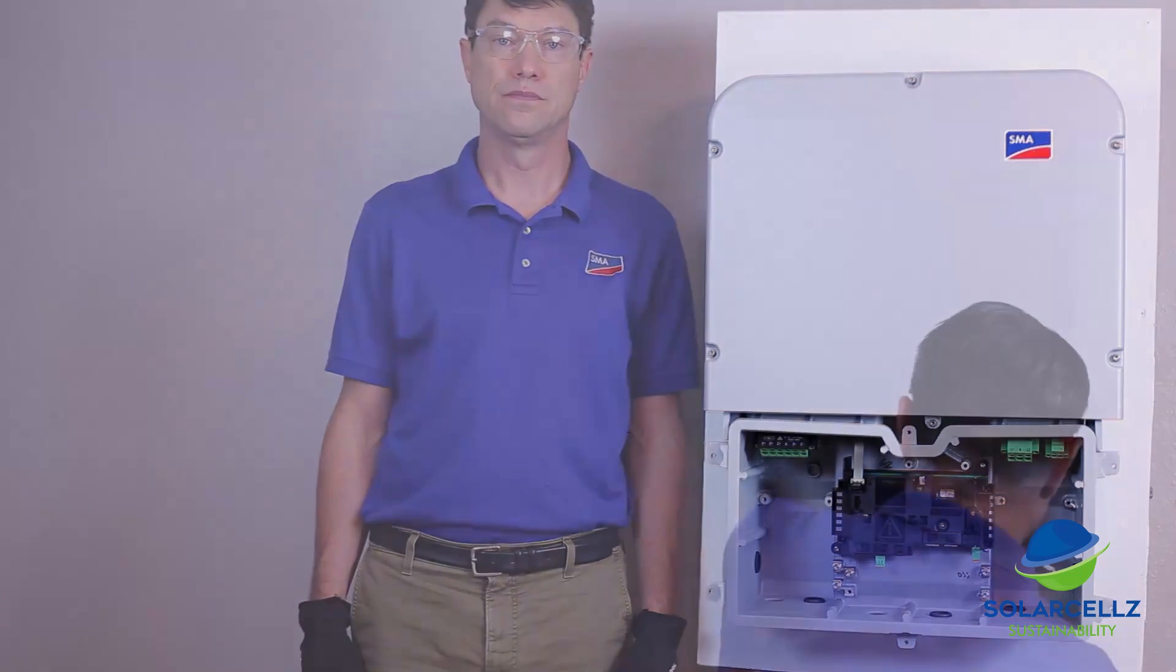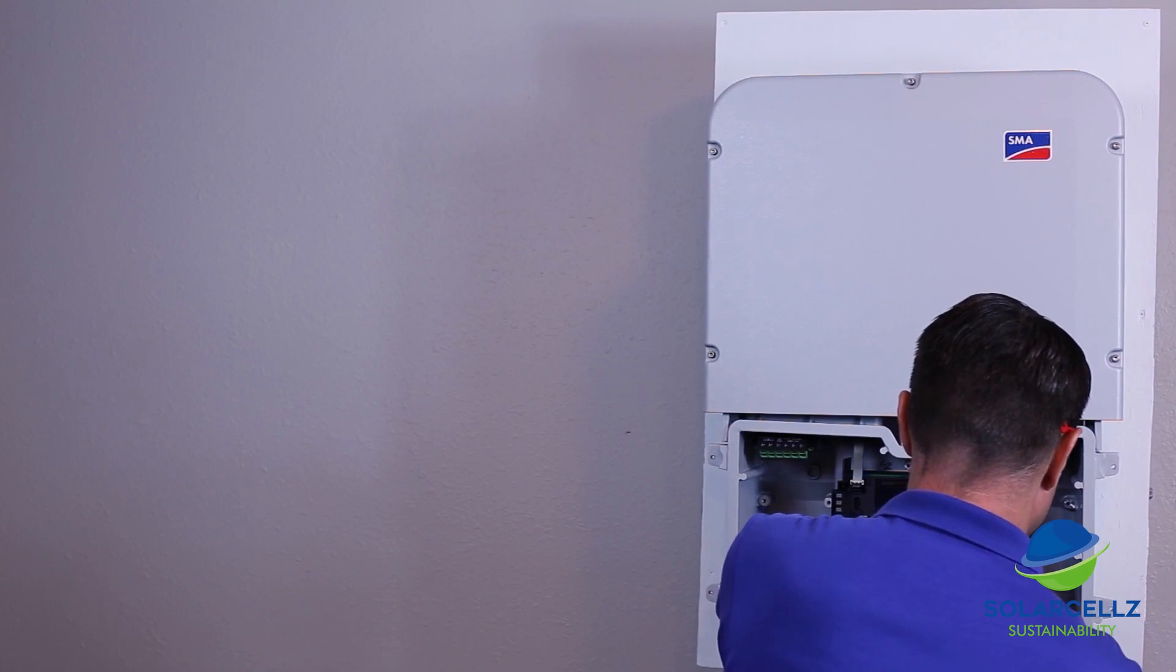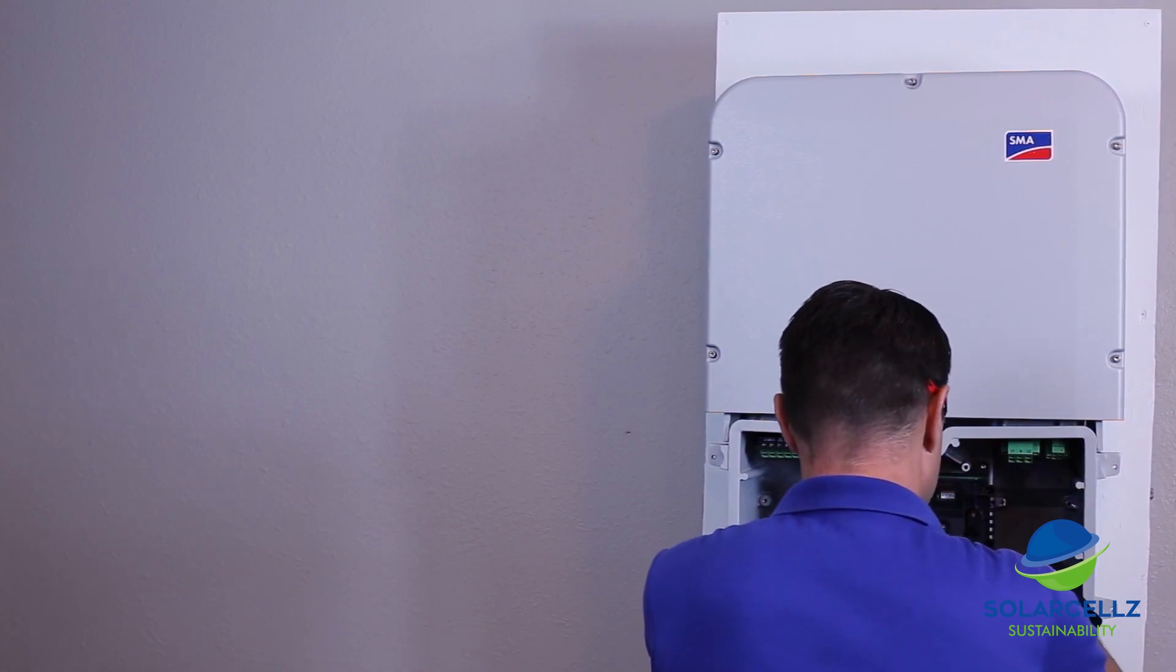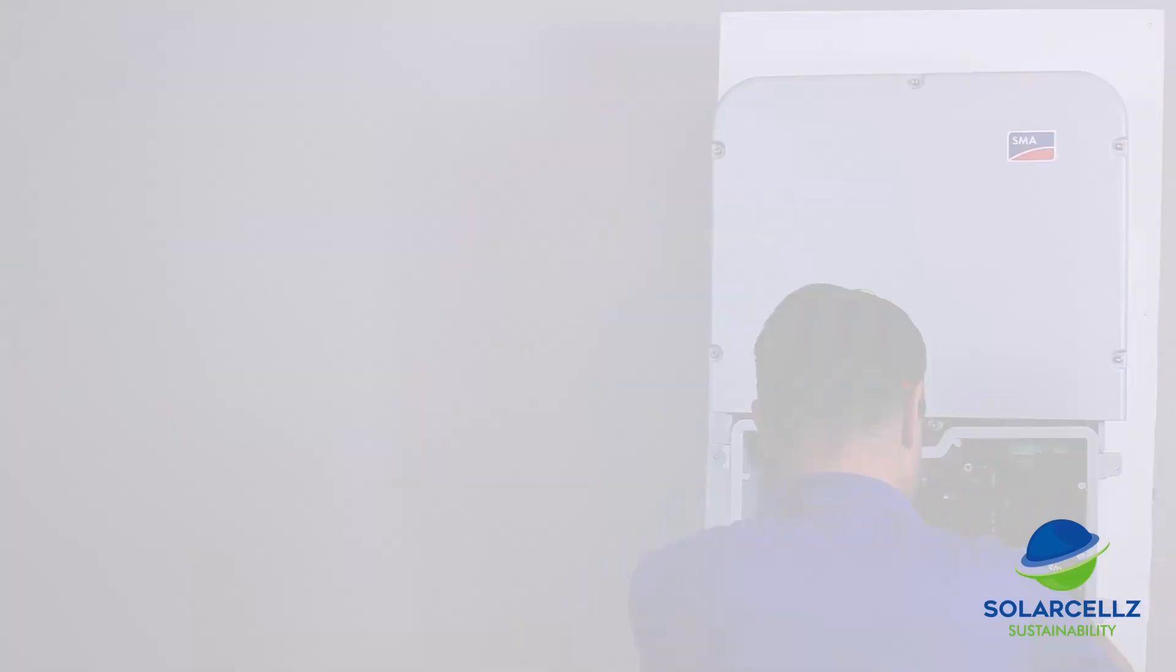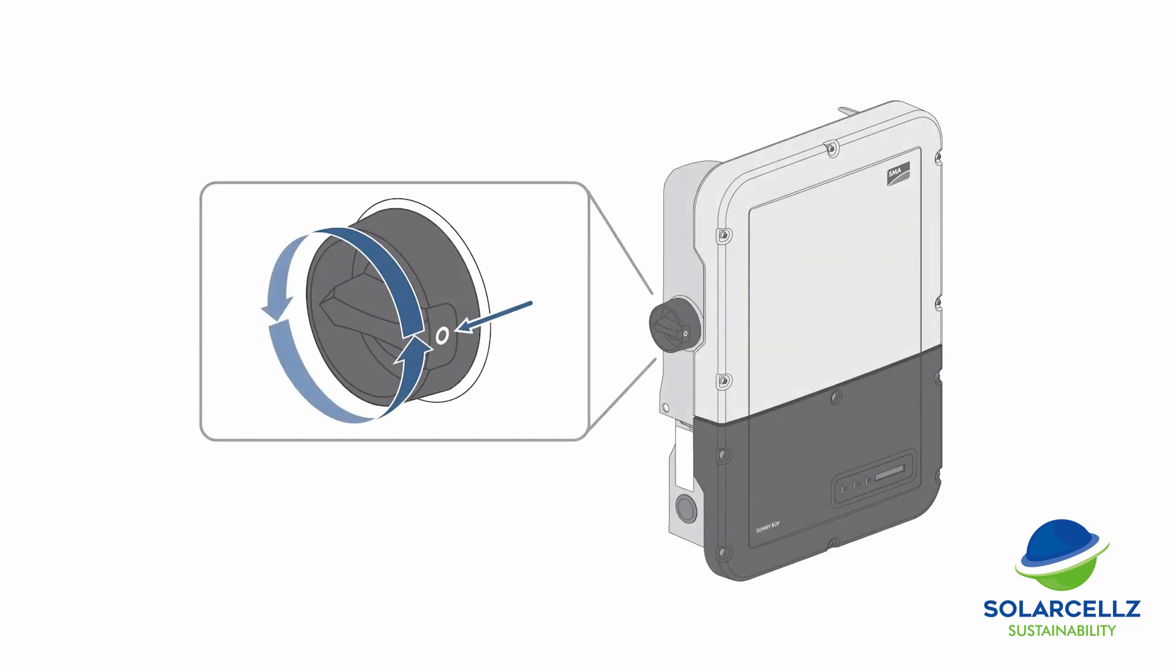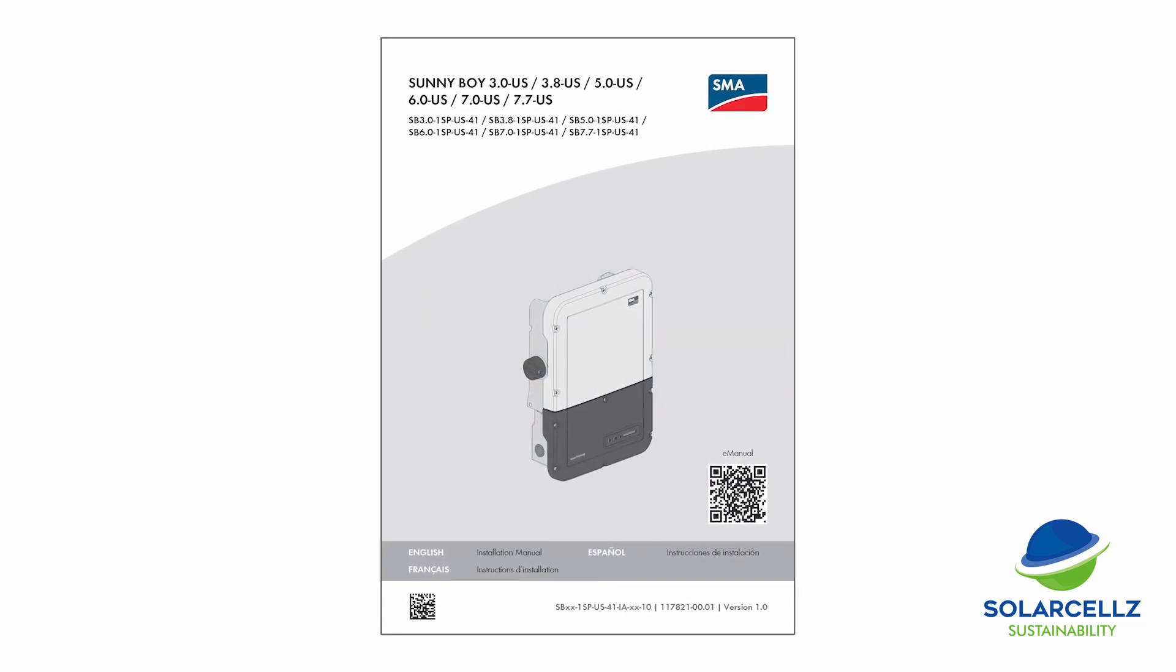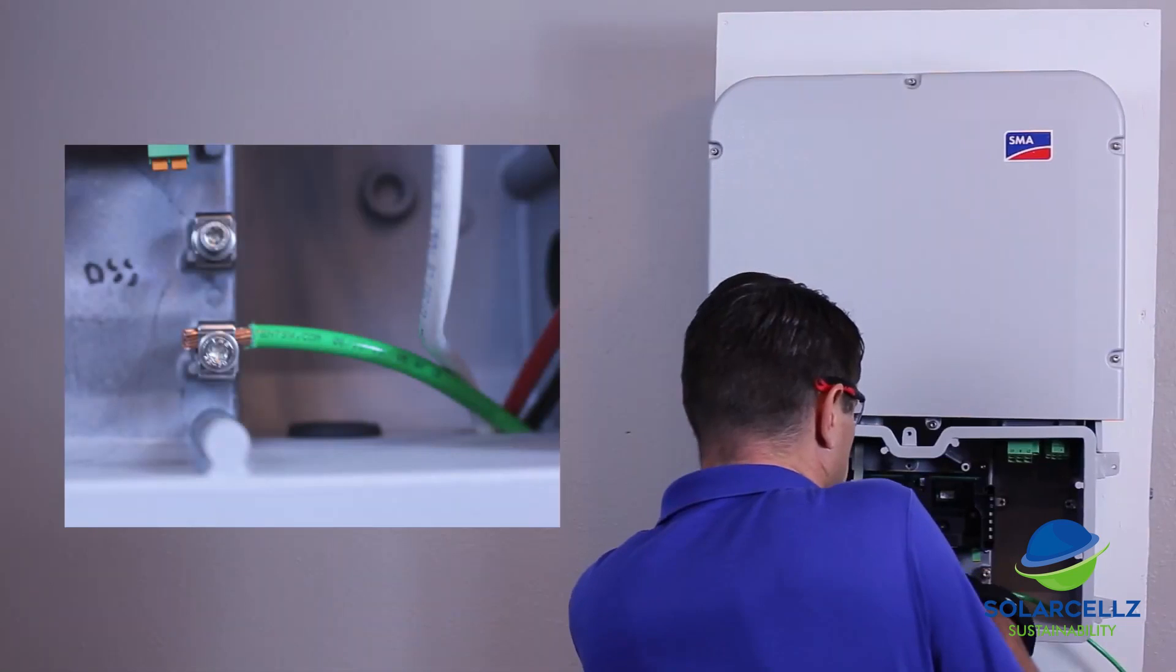For clarity in this video, we're not going to be installing conduit. Ensure all appropriate code requirements are met for an actual install. Once all conduit has been attached with the appropriate fittings, the inverter is ready for the AC and DC conductors to be routed into the connection unit and attached to the appropriate connectors. Ensure the DC disconnect and AC breaker or disconnect are in the off position. Please consult the installation manual section 6 for details on stripping length for conductors and tightening torque for the ground hardware. Start with the AC equipment ground conductor.